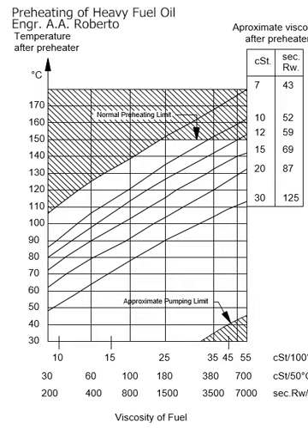But sometimes we receive a bunker with viscosity ranging from 180 to 380 CST. So we need to lower down that viscosity to somewhere between 10 CST up to 15 CST. So that is the recommended viscosity for most marine diesel engines.